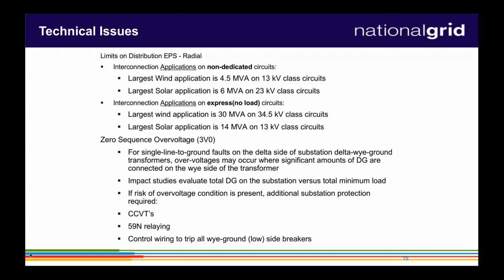With that, we're seeing a large need for 3V0 — upgrading our substation transformers with protection so that we can have reverse power flow. Interestingly enough, another thing not on this slide, but I like to put it in people's minds as food for thought: in substation transformers, first thing is 3V0, so we're protecting them if they're backfeeding. But if they're backfeeding, they're really more of a generator step-up transformer.